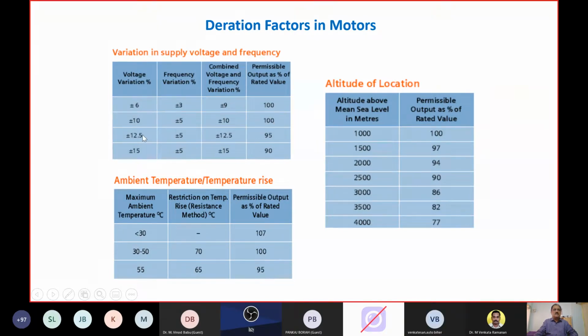But once this deviation goes beyond 10%, the motor needs derating. That means when you select a motor, you have to select a motor with this derating applied. Similarly, for plus or minus 15 and 5, a total 15% variation, the motor output will be derated to 90%. Similarly, for ambient temperatures, up to 50 degree ambient, no derating is required. But once it goes to 55, 5 degrees more, or any part of 50 to 55, 5% is the derating.